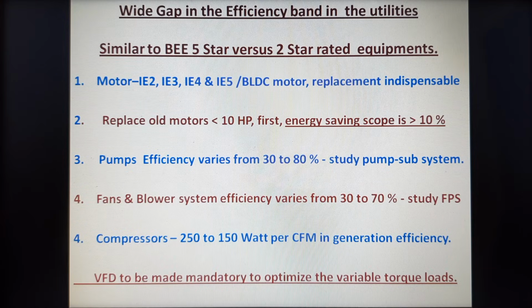Then comes the IE3, IE4 or IE5 motor depending on availability. For BLDC motors, the replacement becomes indispensable, especially for motors less than 10 HP. The pump efficiency varies from the existing pump to the latest generation energy efficient pump, around 30 to 80%. Let us study the pump subsystem also: what pressure is available, what flow is available, what head is available and what is to be delivered. This also applies to the fan and blower system, where we study the fan performance curve and see that the efficiency is around 30 to 40%. How can this be increased to 60 to 70%?